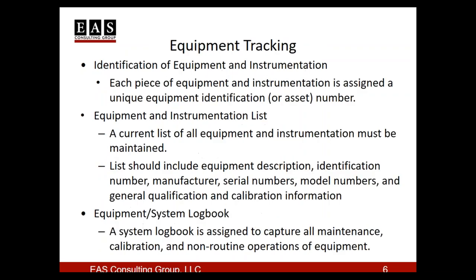So in order to keep track of all this equipment, there needs to be an identification assigned to each piece of equipment and instrumentation. This is sometimes referred to as the asset number, and sometimes there may be two numbers. There may be a number associated in the laboratory and an asset number for the facility itself. Whatever it is, there needs to be a unique identifier for that.